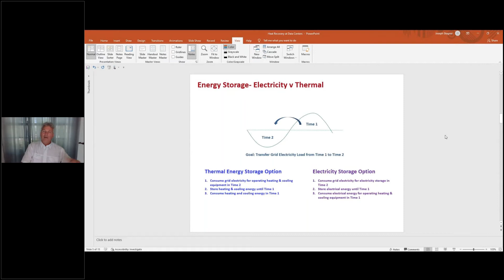That's what thermal storage does for you. It also reduces the capacity of chillers you need. If you had a peak cooling demand of X during a day, you'd need X capacity of chillers, or you could use maybe 0.7X capacity of chillers plus a cold water tank. It's a lot cheaper to build and operate a steel tank that holds cold water than to build more electric chillers.